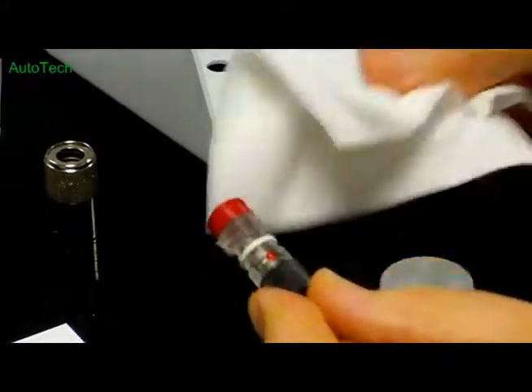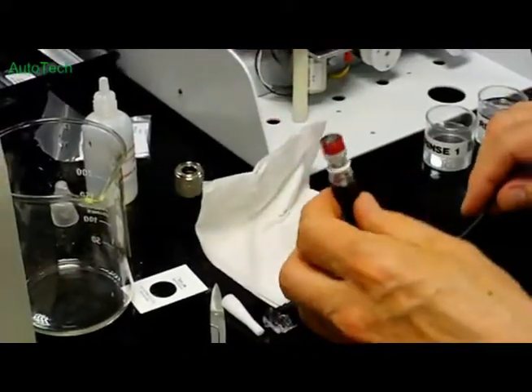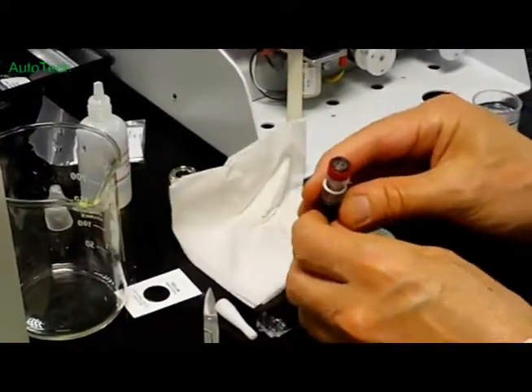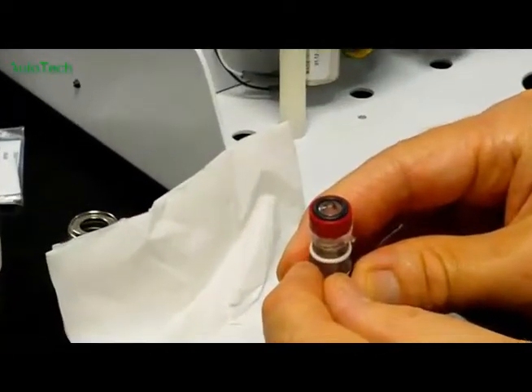Now we're going to inspect the end of the electrode to make sure we have a nice dome appearance to the membrane.